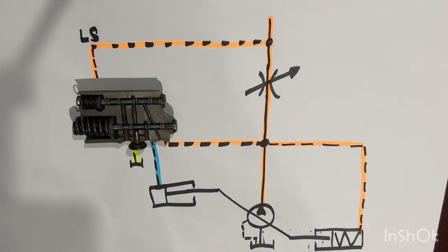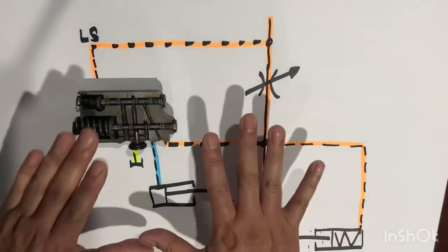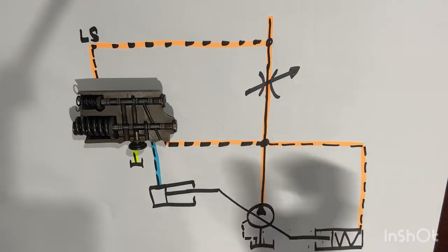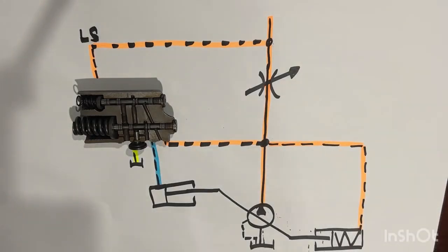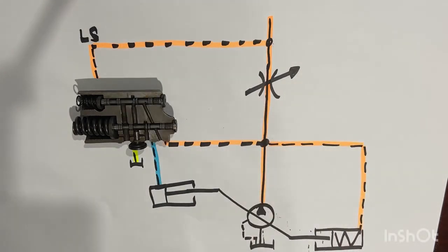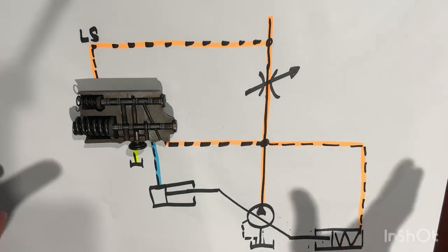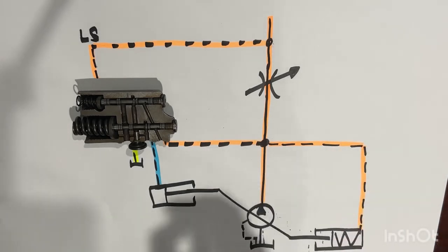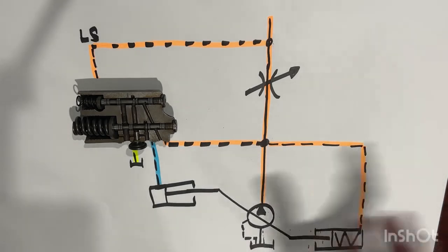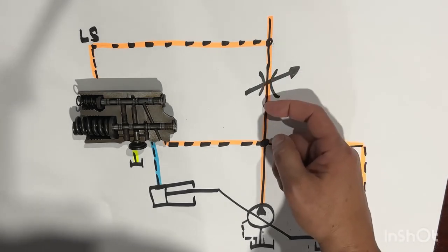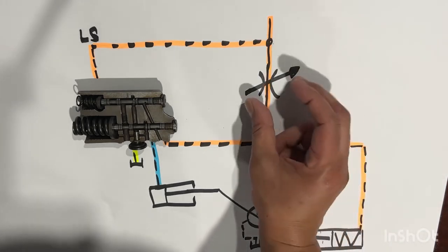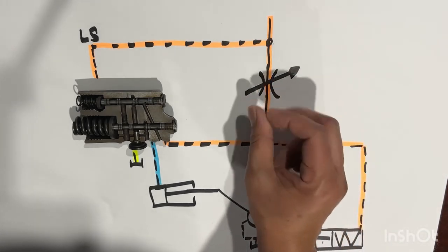Now, condition number 2. Regulation, 50% opening. So from 100%, we go down to 50% opening. What happened here: still unloaded, the pump is still at relatively low pressure. But now the throttle valve is partially closed, from 100% down to 50%.